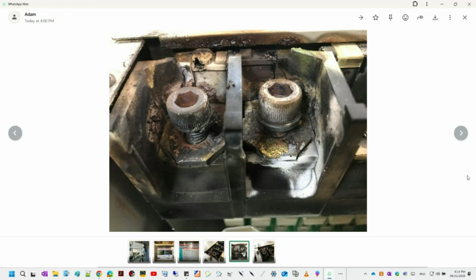But how does that escalate into melted cables and a completely burned out drive? That seems like a huge jump from just a loose bolt. This is where a really critical concept called thermal runaway comes into play. It's a devastating kind of cascading failure mode. You see, a high-resistance connection acts like a bottleneck, like a small electric heater right in the circuit. As all that electrical current flows through it, it generates heat according to that basic physics principle, P = I²R. Power dissipated as heat equals the current squared times the resistance.